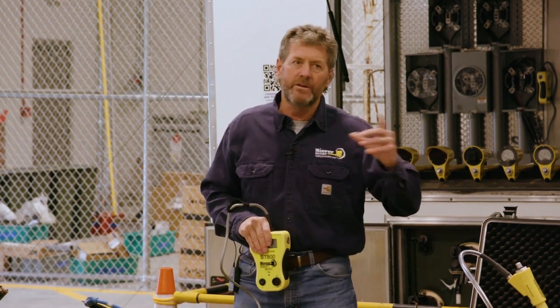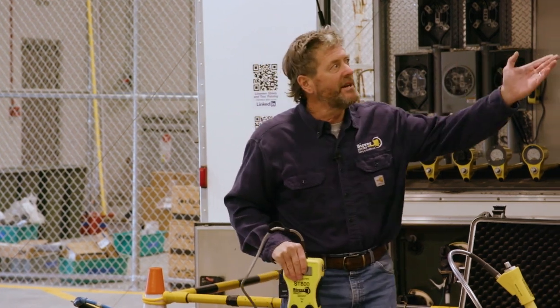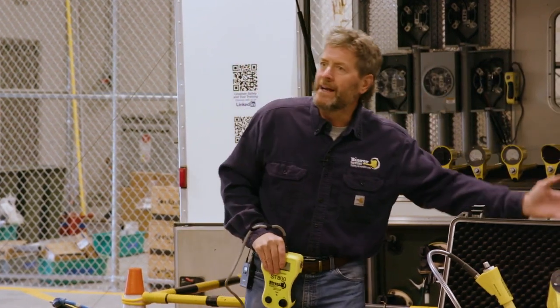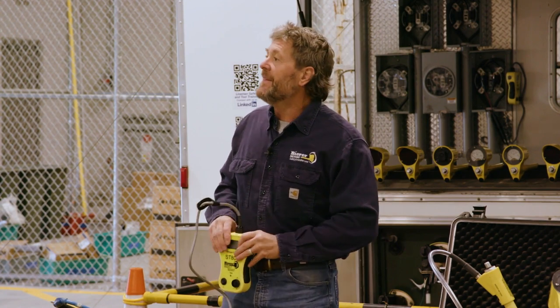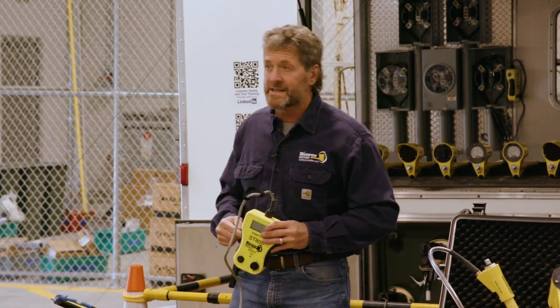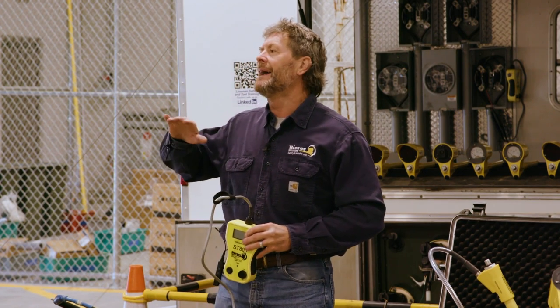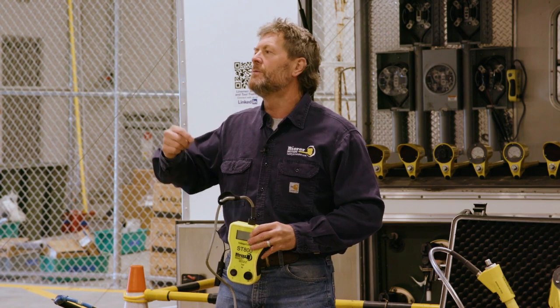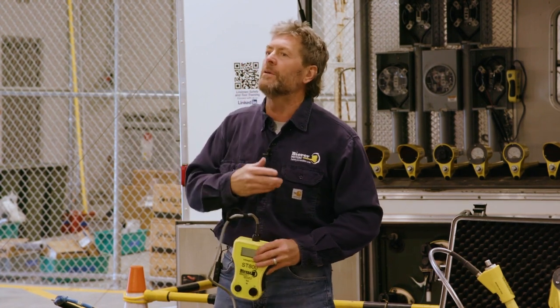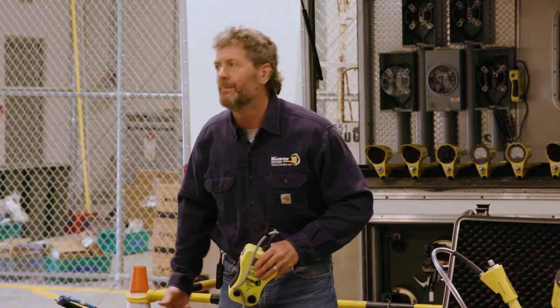You're done. Now we're gonna find that issue on the neutral, retest it, discover it, turn it off, and make your repair, then retest. The reason you retest is because this tool sources 800 milliamps. You can find a problem in that circuit before the customer calls you back out 2 or 3 years later, telling you they've got another problem.